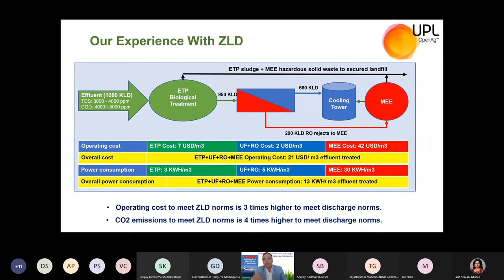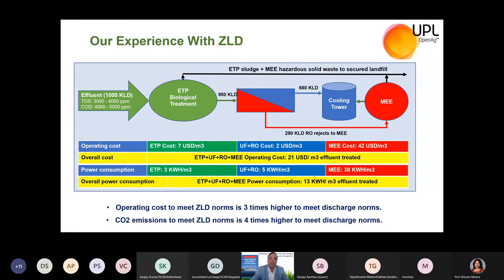If you have a good stream available where you can discharge treated effluent and just meet discharge norms, you only need to adopt ETP with biological and physical treatment — no need to adopt ZLD. Then your cost of treatment will be nearly three times lesser than the cost of ZLD. Power consumption with MEE is very high at nearly 30 kWh per cubic meter, with UF/RO at 5 kWh per cubic meter, and ETP at 3 kWh per cubic meter.